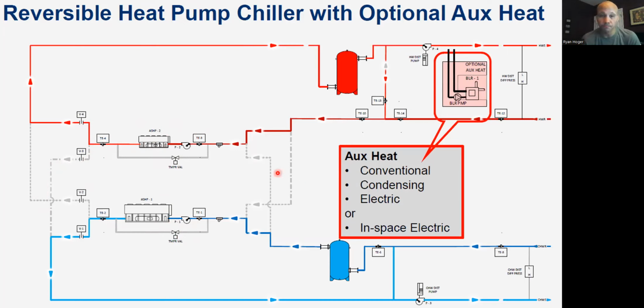Something like that. On the heating loop, I can also have supplemental heaters on there. Now, if I sized everything for 110 degree water or whatever, I might not need this. But if the building's existing and I was expecting 180 degree water to all the heating devices, and I don't want to change out all the heating devices, but I do want to do the heat pump chiller, then what I can do is have an additional heater that supplements this loop. In this case, there's a gas-fired boiler that's dumping heat into this loop. That would be probably for your climate the most efficient way to do it.